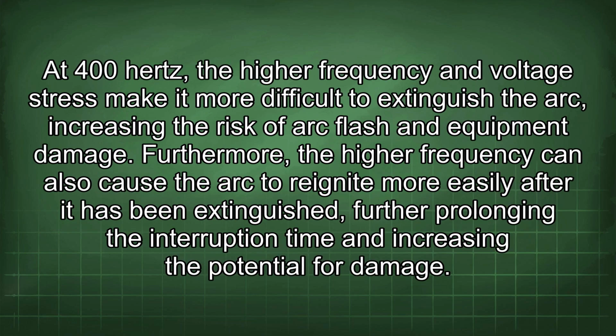At 400 Hz, the higher frequency and voltage stress make it more difficult to extinguish the arc, increasing the risk of arc flash and equipment damage. Furthermore, the higher frequency can also cause the arc to reignite more easily after it has been extinguished, further prolonging the interruption time and increasing the potential for damage.